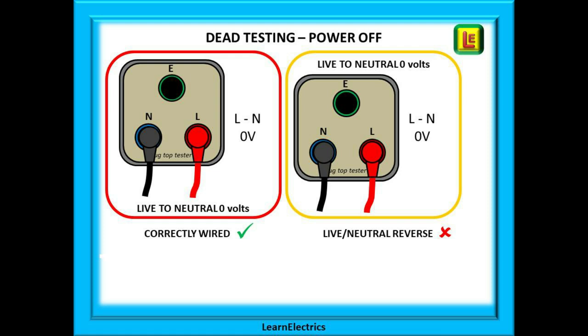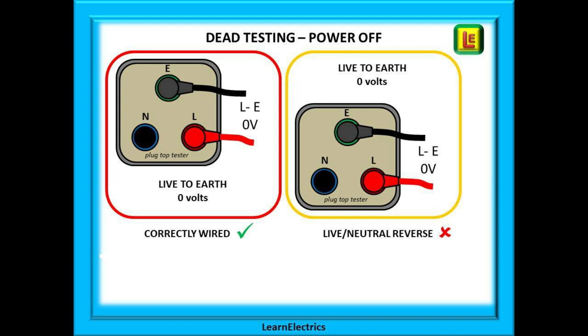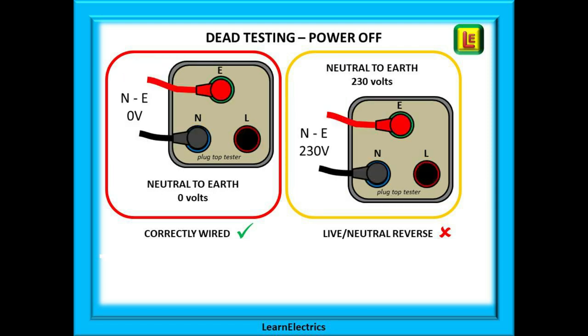Now safely isolate the circuit at the MCB and lock it off. We are now testing for dead. We've shown here side by side the results for a good circuit on the left and for a reverse wired circuit on the right. You can see that both show zero volts between live and neutral. Between live and earth shows zero volts in both cases. But when we test neutral to earth, the reverse wired circuit shows 230 volts and not zero volts. To work on this faulty circuit right now would be dangerous, possibly fatal.